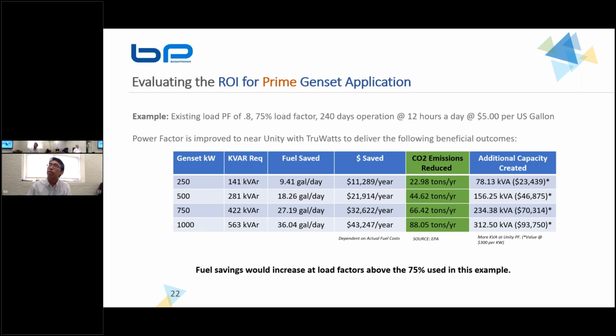And one thing to note here is it's very specific on a case-to-case basis. So in this example, we're assuming that your load is running at 75% and your power factor is at 0.8, which is 80%, and assuming you're only running for 240 days in a year for about 12 hours a day and $5 per US gallon, these are the values that we get. And as you can see, we can reduce carbon emissions by a couple of metric tons over a year, depending on how big your genset is. And one thing to note is the more often you run your generators, the more savings you'll see, right? Because this is on a per hour basis. The more you run your generator, the more savings you'll see throughout the year when you're reducing that incremental increase from heating.